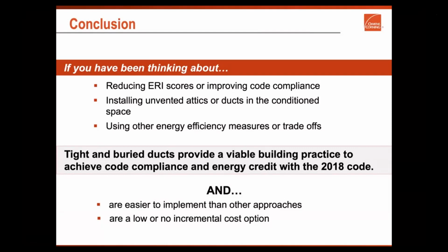We need to do a manual J, D, and S to make sure that we're going to comply properly, and you're going to properly size it based on buried ducts. And then on top of that, air leakage. You know, a lot of them, even if they do a manual J, most people end up sticking to that standard, you know, 5-7 ACH50 that's set in the program, rather than actually changing it to what it would be, right? Can you imagine how many homes are being oversized in climate zone 3 that are required 3 ACH50 versus, you know, San Antonio that required 5?